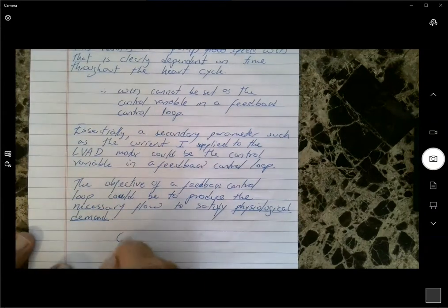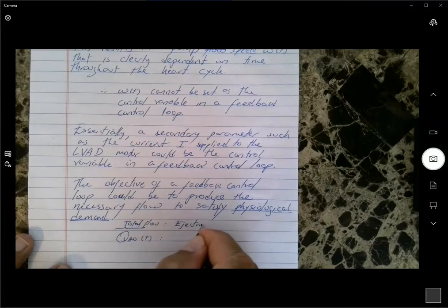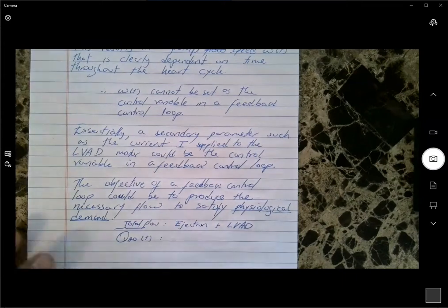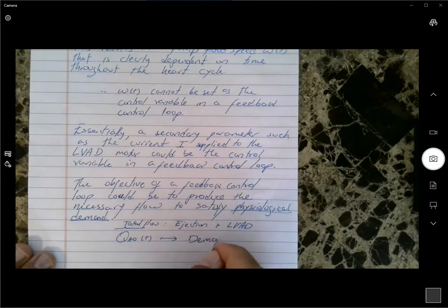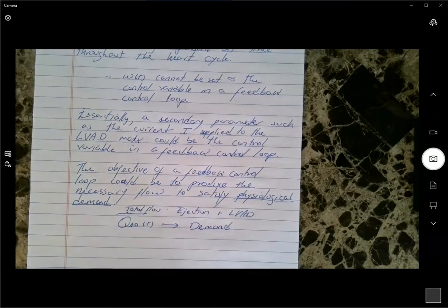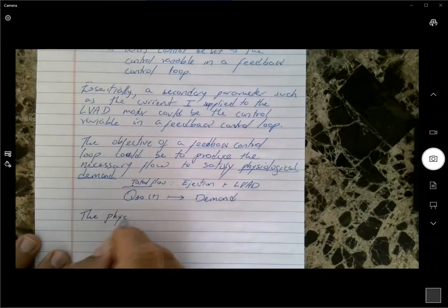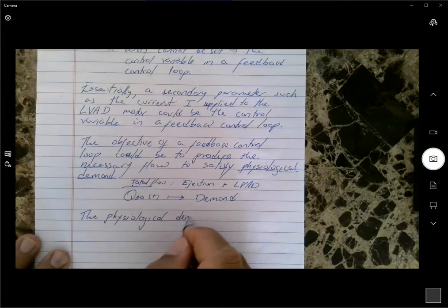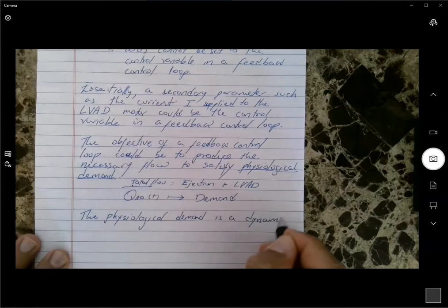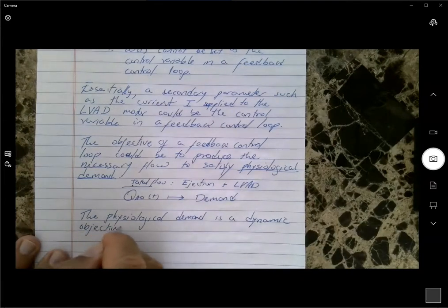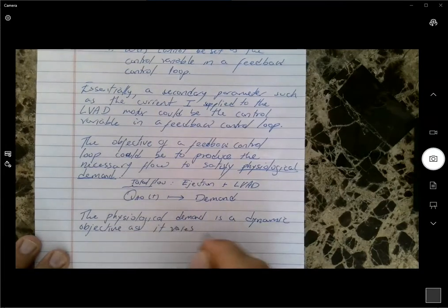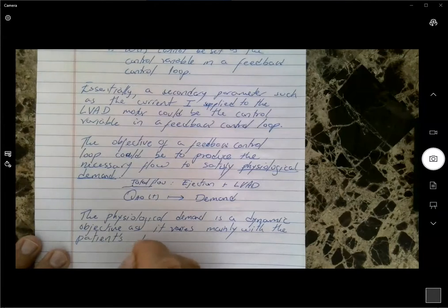So basically, Q_AO, which is the total flow, is ejection plus what the LVAD is producing, should be targeted to satisfy the demand. So the physiological demand is a dynamic objective, as it varies mainly with the patient's level of activity.